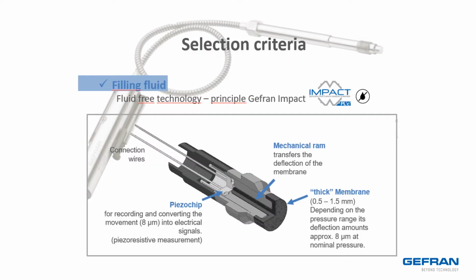In addition to this extensometric sensor design, Gefran has also developed a piezoresistive, solid-state, fluid-free melt sensor called Impact that provides more performance than any other sensor on the market and eliminates any concern over fill material. It is operable at temperatures as high as 350 Celsius. It features a diaphragm many times thicker than a standard melt sensor, ideal for challenging mediums and long duty cycles. It has a floating hex nut, allowing for easy installation. Temperature compensation is built in, and a PL Level C version is available.